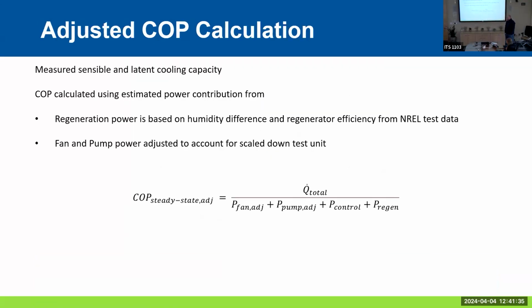So we ran it through all these different conditions, and we wanted to understand how the efficiency worked for the system. This is generally looked at as a coefficient of performance, or COP. We took the total energy cooled and divided that by the fan usage and the pump usage. Because this was a scaled down unit, we had a little bit of adjustment to each of those. And then the amount of energy used to control the system, which was very little, just the brains of the whole operation. And then here we use the regenerative power, which we got some details from tests that were done on a similar system at NREL. If we wanted to look at just the real-time situation, we would run this same calculation without the regenerative power that was used. And that got some really high numbers because most of the energy is used from the regen.